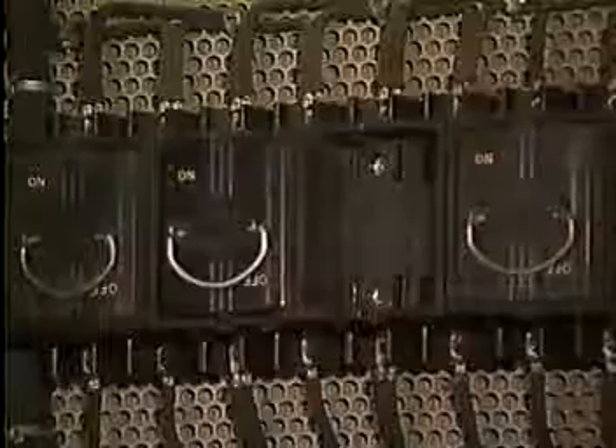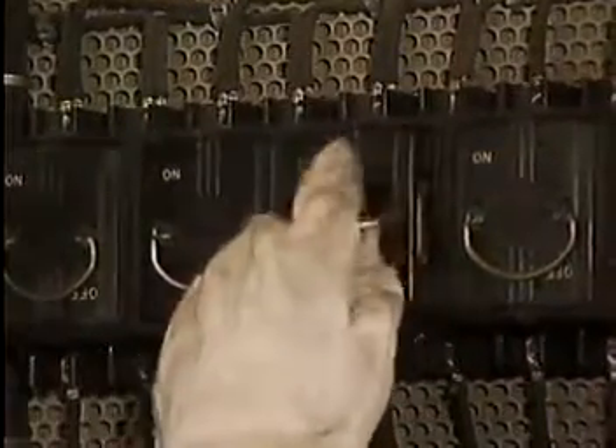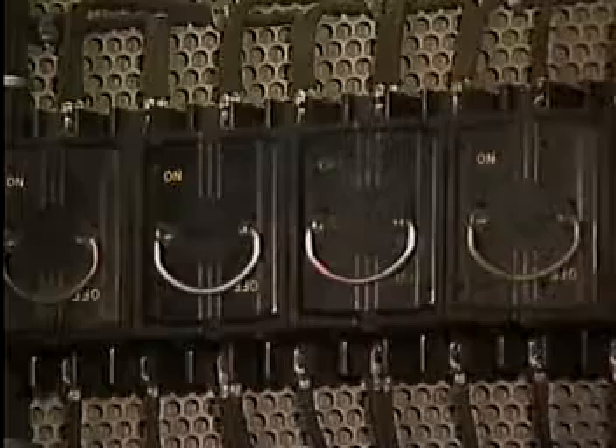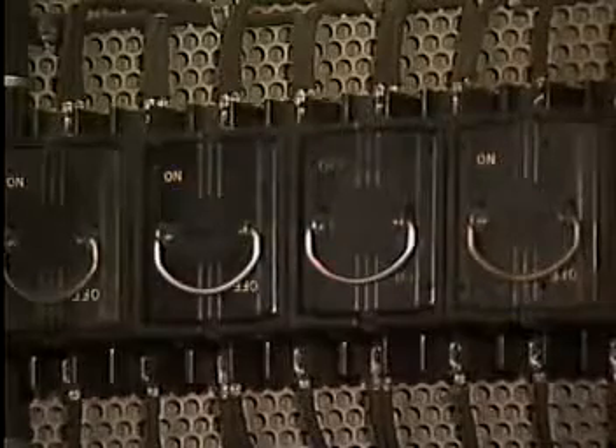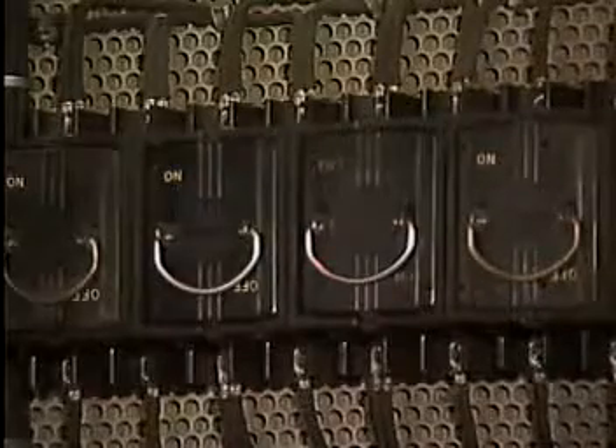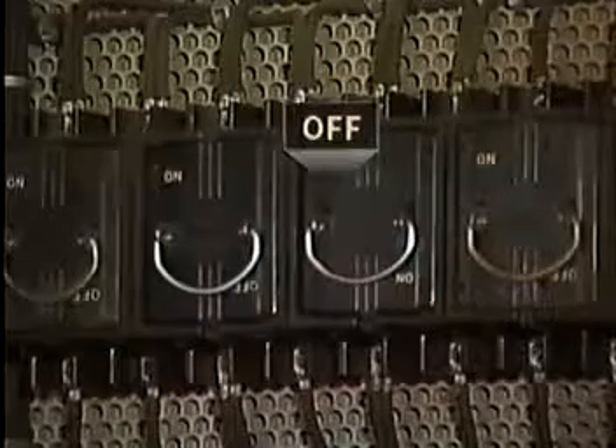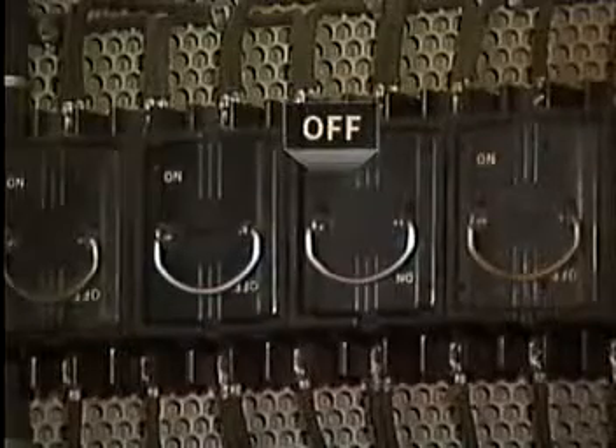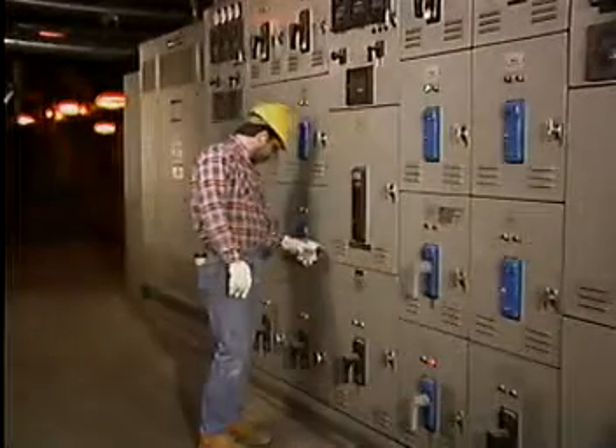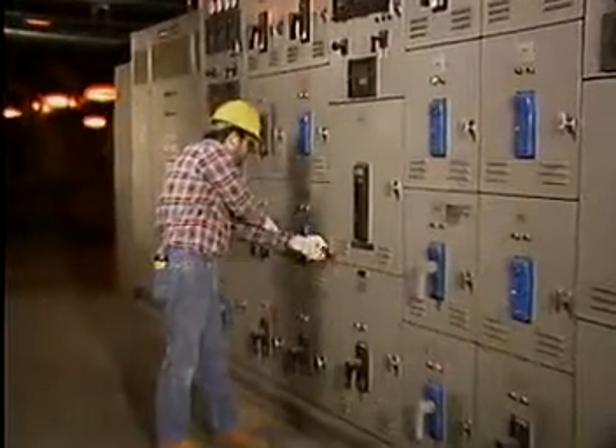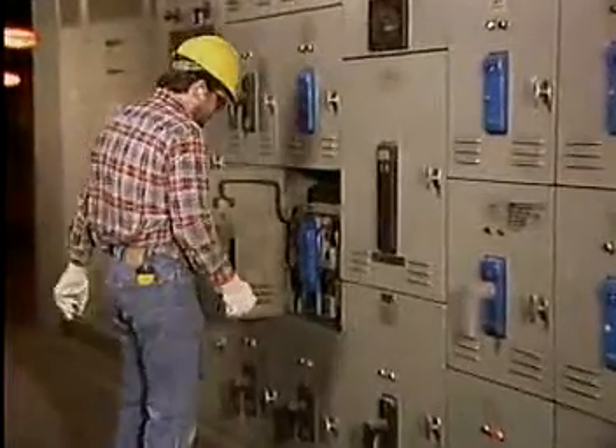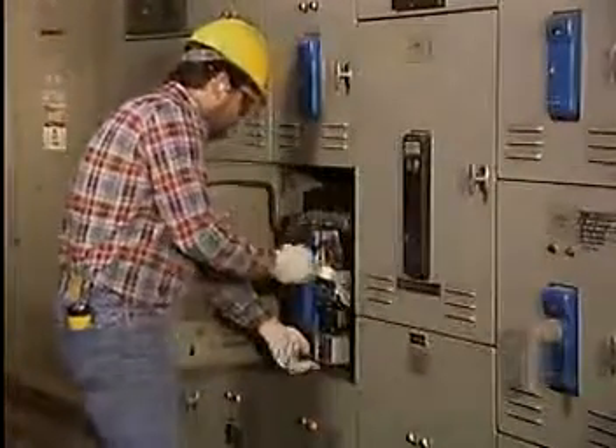For this breaker, the operator reinserts the fuse block upside down. This maintains a physical break in the control circuit, so the breaker can't be operated. The off label indicates that even though the block is in place, the circuit is still de-energized. Now the breaker can be physically disconnected. Here, that's done by releasing a latch and sliding the breaker out of its enclosure. An indicator on the side of the enclosure shows when the breaker has been disconnected.